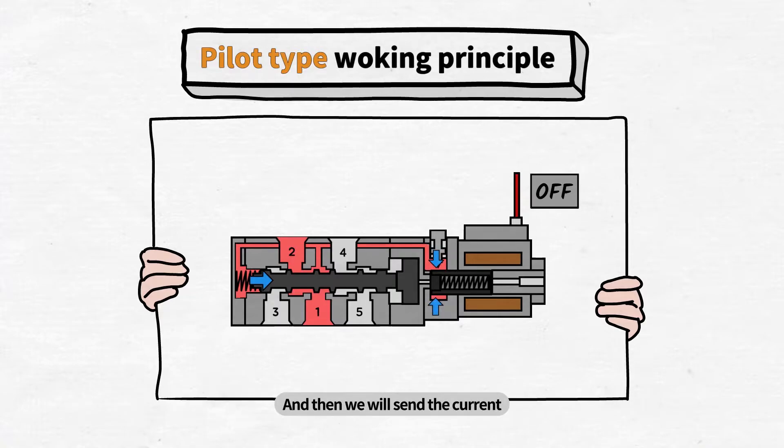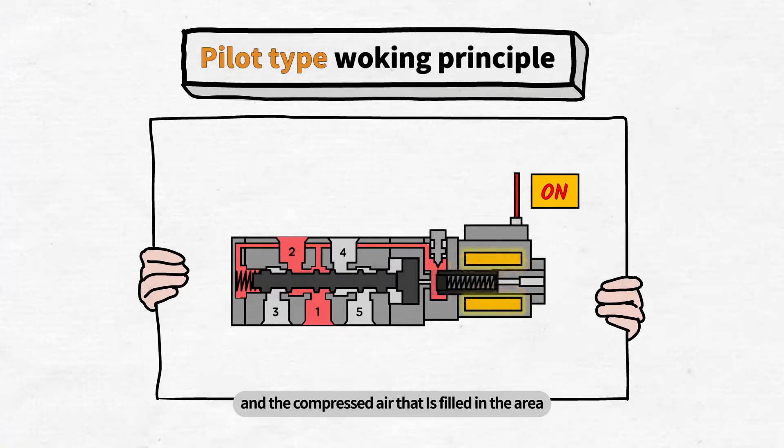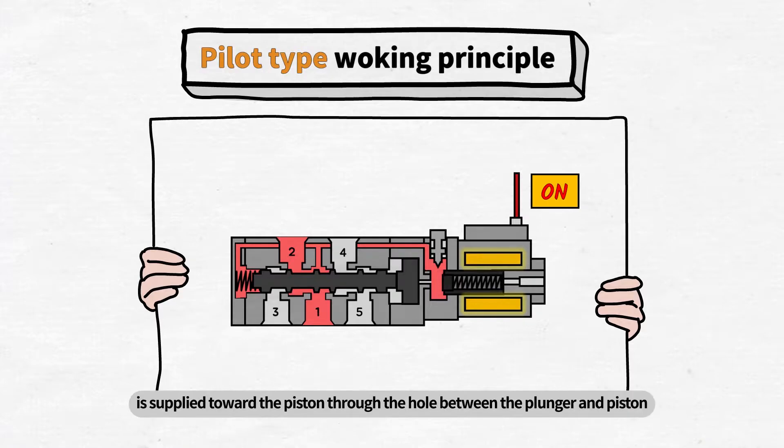And then we will send the current. Once the current begins to flow, the plunger is pulled by magnetic force and the compressed air that is filled in the area is supplied toward the piston through the hole between the plunger and piston. The compressed air then pushes the piston and spool.